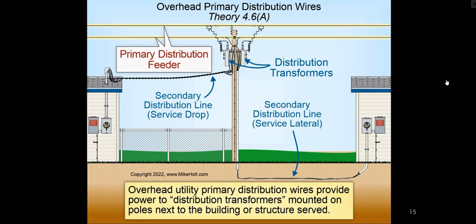And if you look at this, here's the primary distribution feeders up there at the top. And then you have the distribution transformers. And notice where it says the secondary distribution line. In most cases, the utility company is responsible for what is termed the service drop. In other words, it's dropping here to the service mast on this structure, and then down into the meter base, through the disconnect, and into the structure.